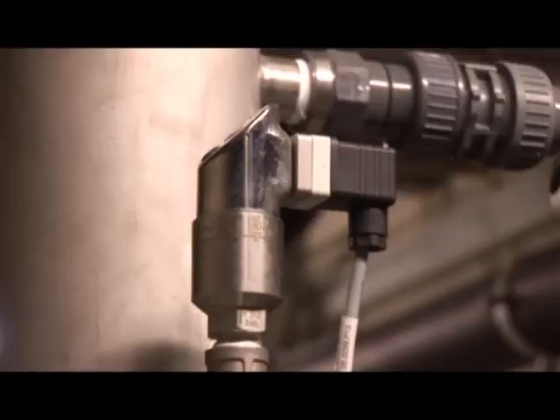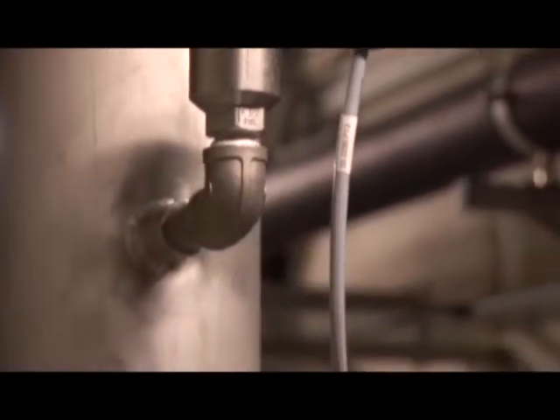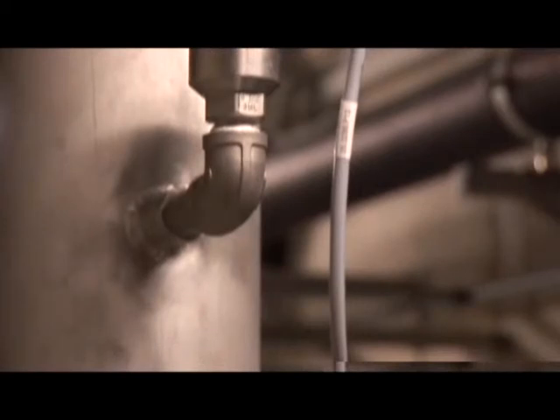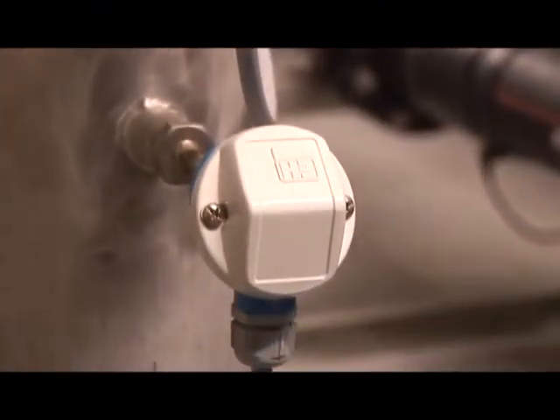Membrane filtration is installed with a 4-chamber system. Media supply is extensively instrumented. Filtrate transport is done through the membrane to the interior. This is done through a vacuum imposed on the membrane. The level in the membrane chambers is hydrostatically monitored with Cerabar T sensors.